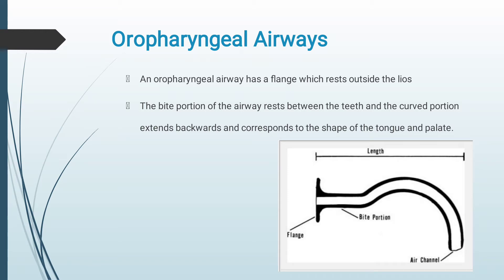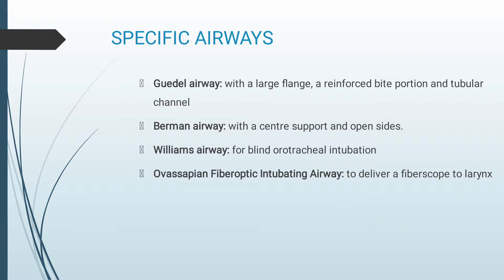Starting with oropharyngeal airways. An oropharyngeal airway has a flange which rests outside the lips. The bite portion of the airway rests between the teeth and the curved portion extends backwards and corresponds to the shape of the tongue. Specific types include: Guedel airway with a large flange, a reinforced bite portion, and a tubular channel; Berman airway which has a center support and open sides; Williams airway which is used for blind orotracheal intubation; and Ovassapian fibre-optic intubating airway which is used to deliver a fibroscope to the larynx.